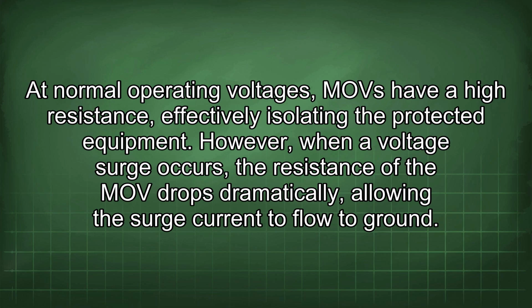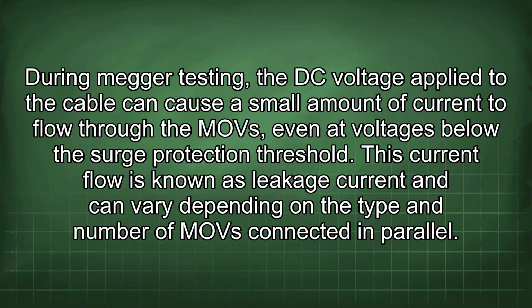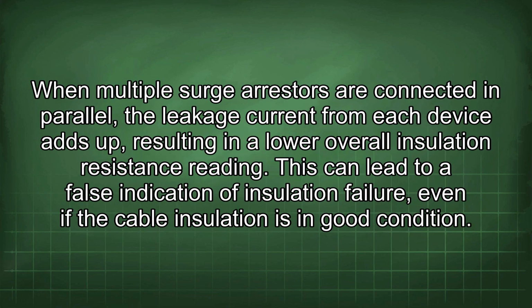However, when a voltage surge occurs, the resistance of the MOV drops dramatically, allowing the surge current to flow to ground. During Megger testing, the DC voltage applied to the cable can cause a small amount of current to flow through the MOV, even at voltages below the surge protection threshold. This current flow is known as leakage current and can vary depending on the type and number of MOVs connected in parallel. When multiple surge arrestors are connected in parallel, the leakage current from each device adds up, resulting in a lower overall insulation resistance reading. This can lead to a false indication of insulation failure, even if the cable insulation is in good condition.